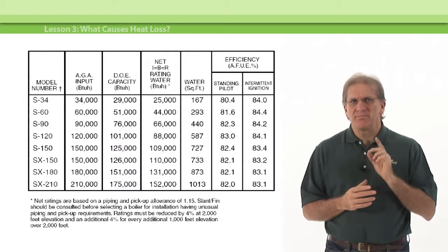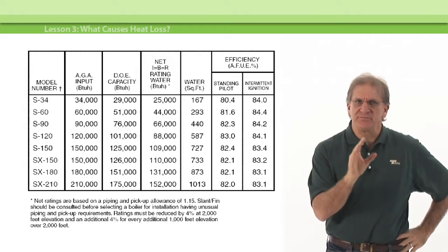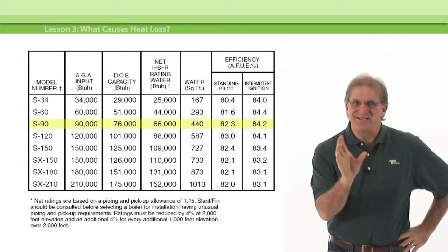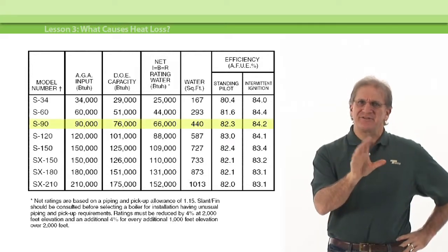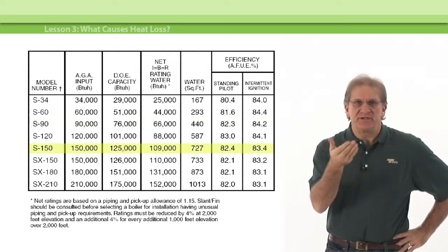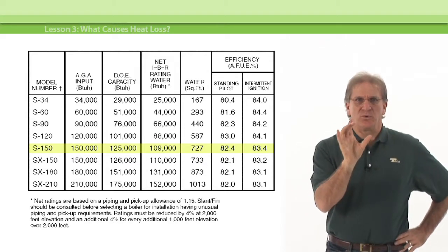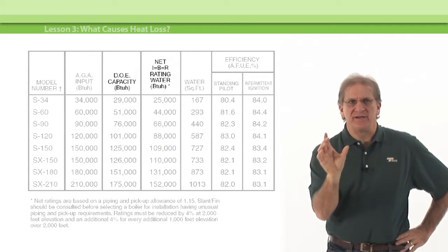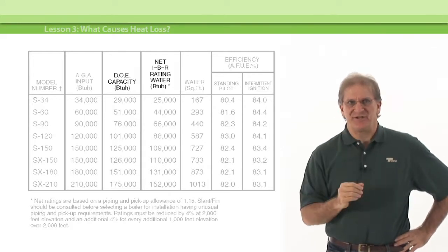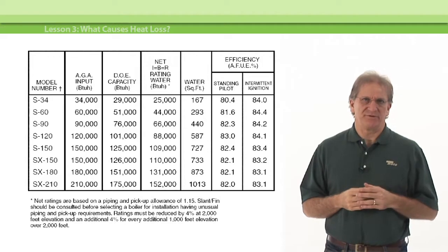Now, one quick word about boiler sizing. When you go to choose a boiler based on your total heat loss for the building, you don't have to add a safety factor, really. A safety factor is already built into the data that we're going to be using, and it's also built into common boiler ratings, like those that boiler manufacturers put out, or the net IBR ratings, or the U.S. Department of Energy capacity ratings. Now, this applies equally to new systems or to replacement boilers.